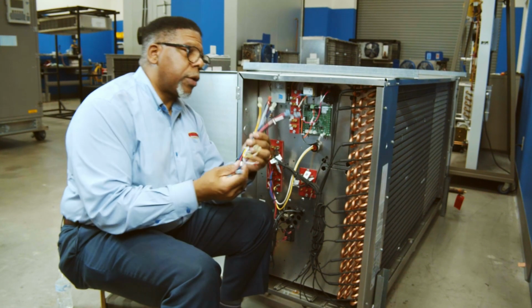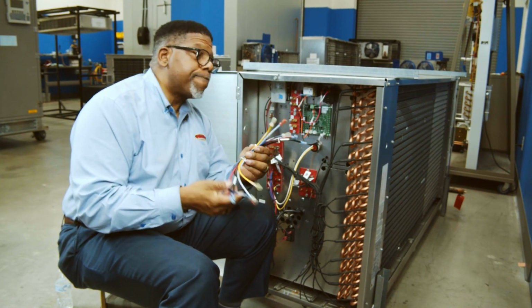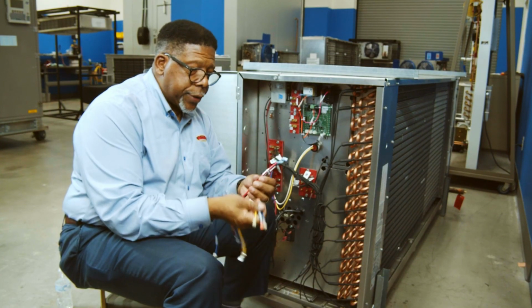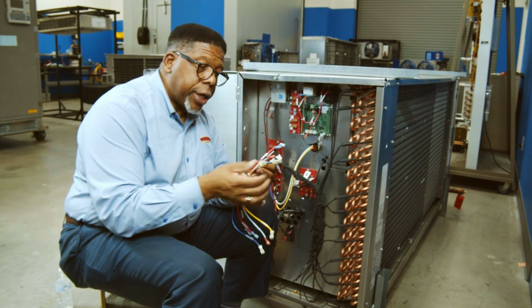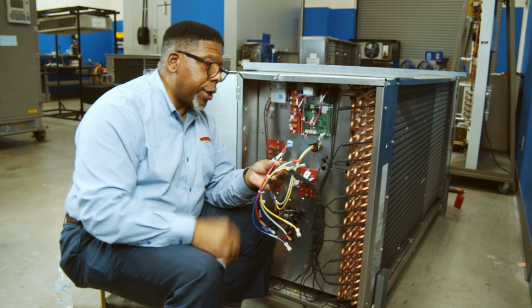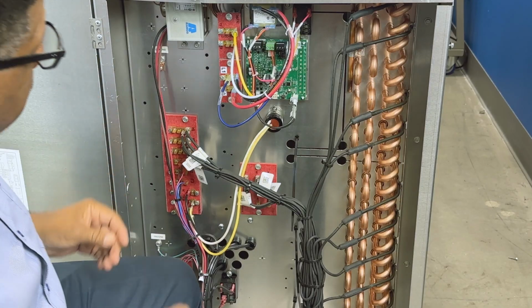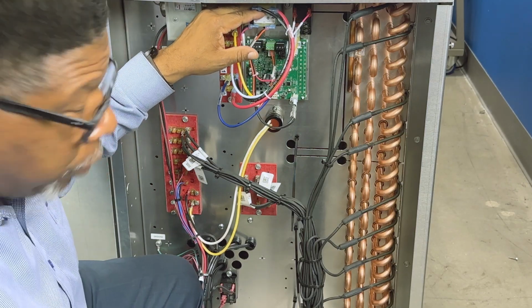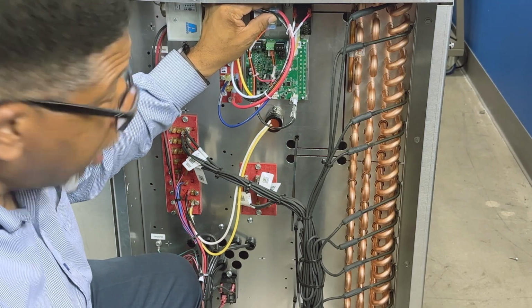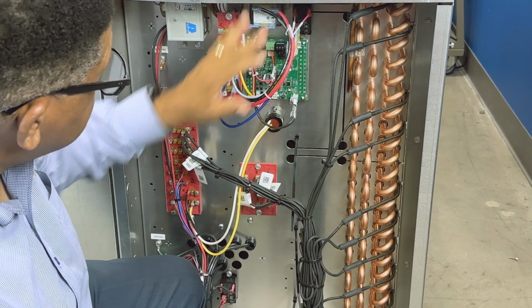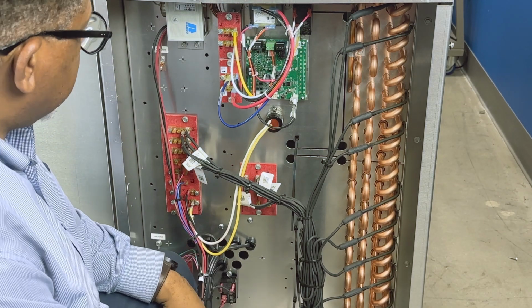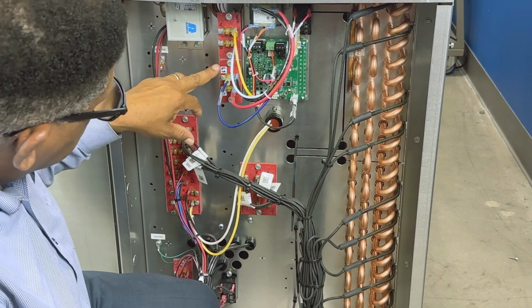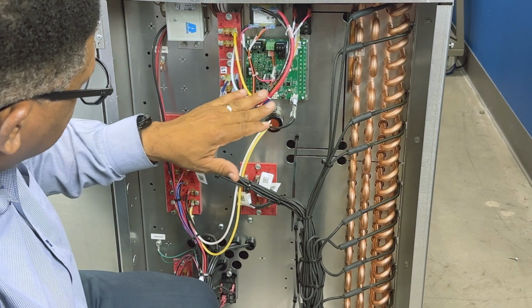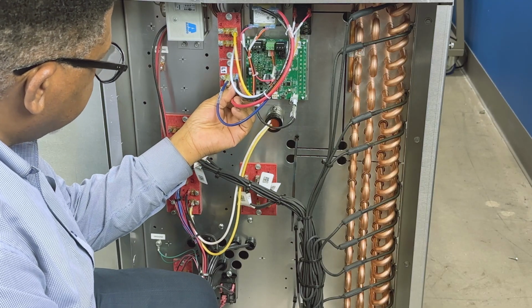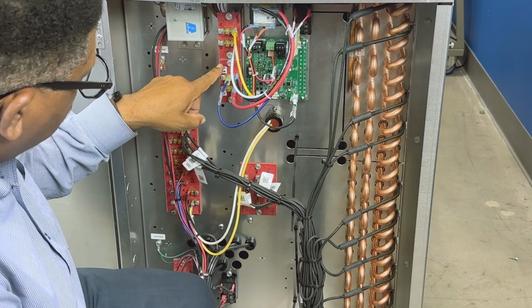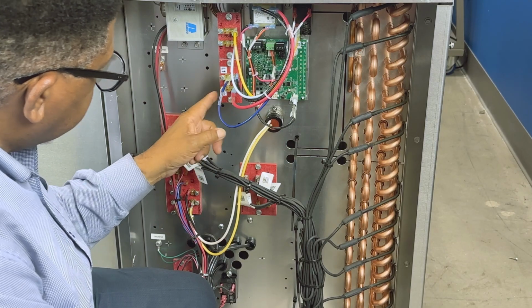Let's go ahead and connect our high voltage wire harness. To start with that, let's go with this. Everything, remember, is color coded and it has a number associated with that. Now we've got our primary voltage at 1 and 2, so that's your black wire and your red wire. You've got your voltage for L1 and L2, the other side of the black wire and red wire. Black goes to L1, red to L2.